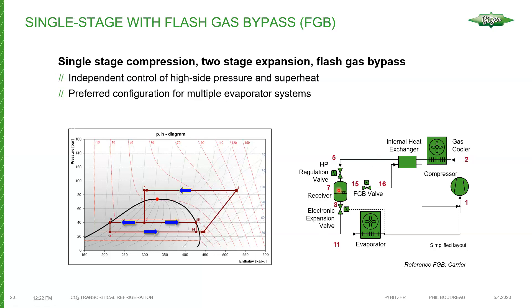A modified single-stage cycle introduces a receiver on the high side. An expansion valve throttles to maintain specific superheat at the evaporator outlet, ensuring good control and superheated refrigerant returning to the compressor. Note that superheat leaving the evaporator is generally not high enough for the compressor inlet — this is where lubrication problems occur, as CO2 dilutes oil to the point where viscosity is too low for adequate lubrication. The flash gas and liquid separate in the receiver — flash gas stays at the top, liquid drops to the bottom and is fed to evaporators. This is a preferred method when using multiple evaporators, involving single-stage compression and two-stage expansion.